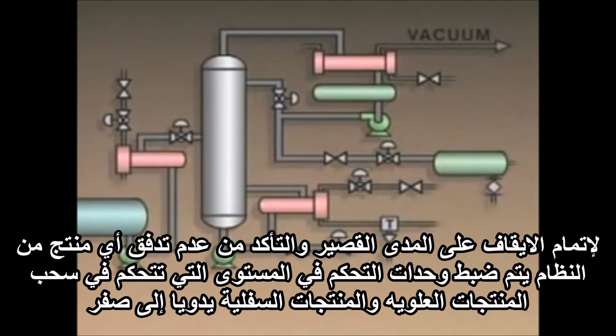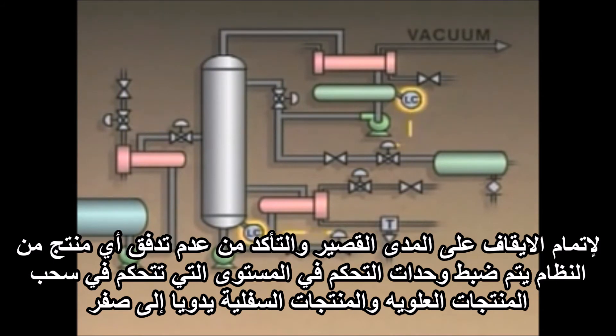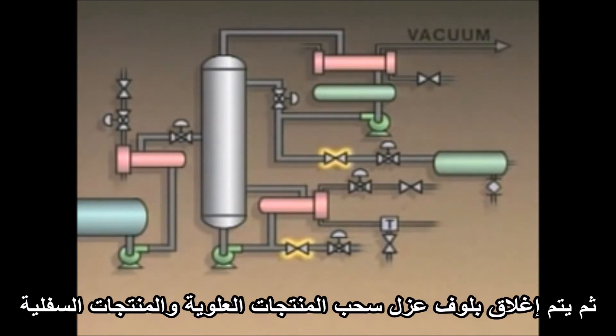To complete the short-term shutdown and ensure that no product flows from the system, the level controllers that control the takeoff of overhead product and bottoms product are manually set to zero. Then, the isolation valves in the overhead product and bottoms product takeoff lines are closed.